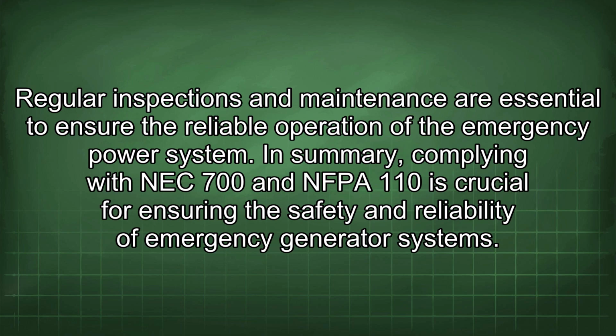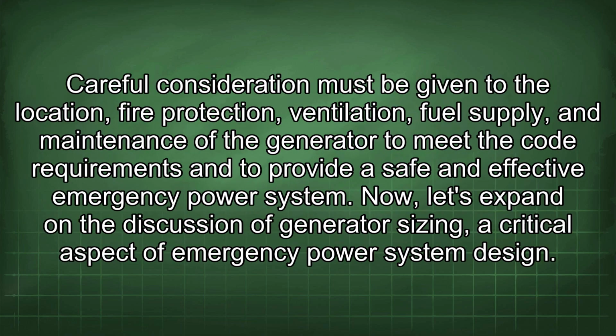In summary, complying with NEC 700 and NFPA 110 is crucial for ensuring the safety and reliability of emergency generator systems. Careful consideration must be given to the location, fire protection, ventilation, fuel supply, and maintenance of the generator to meet the code requirements and to provide a safe and effective emergency power system.